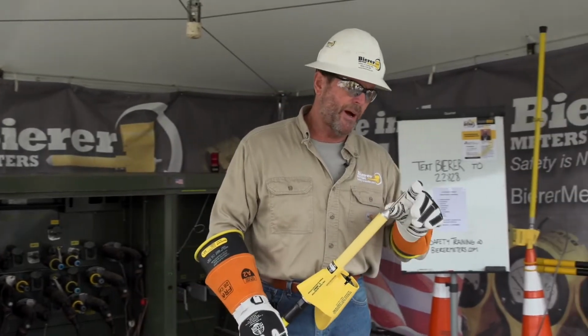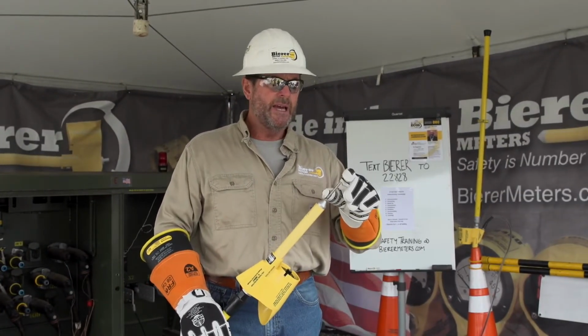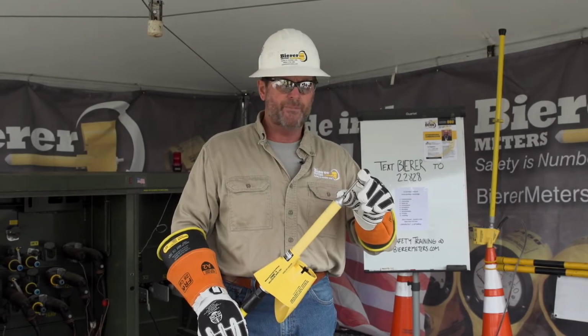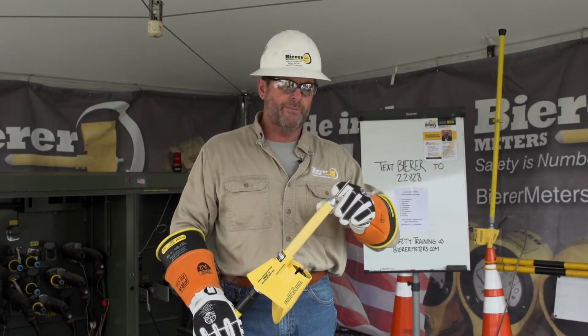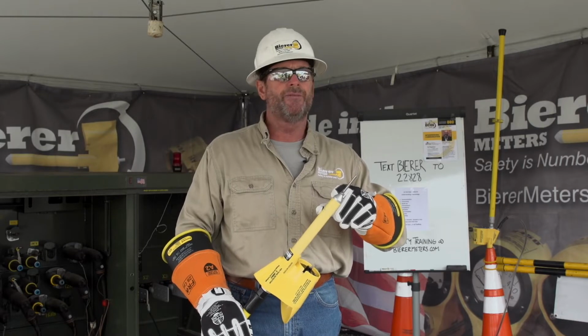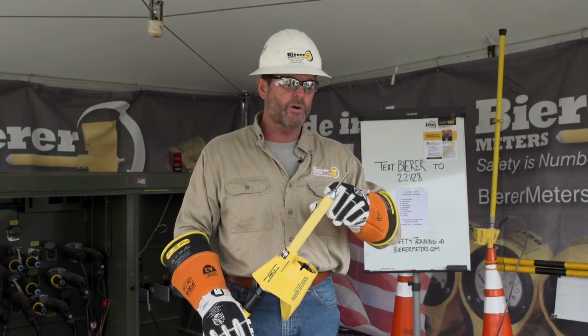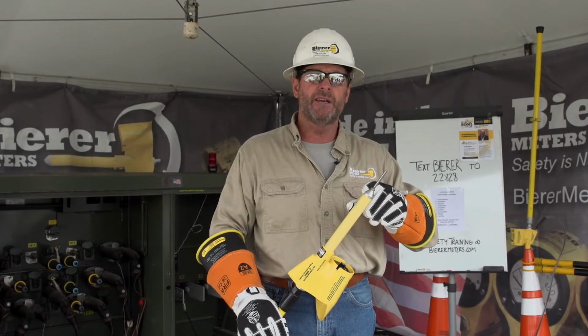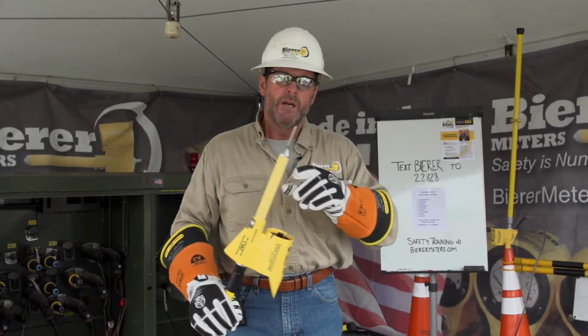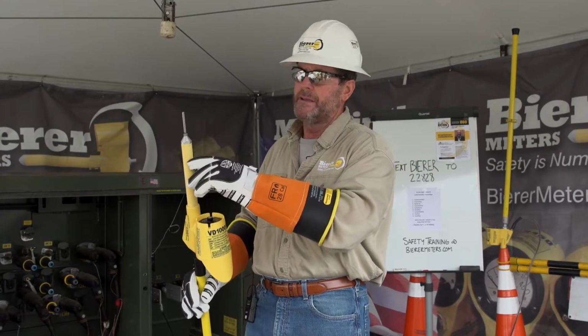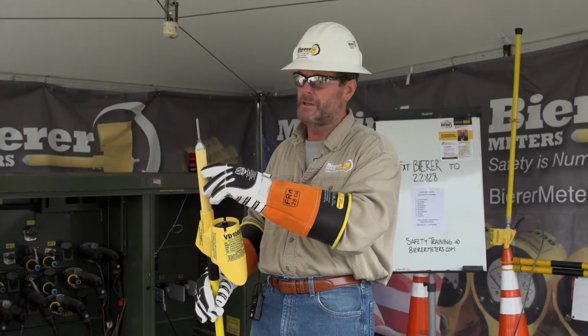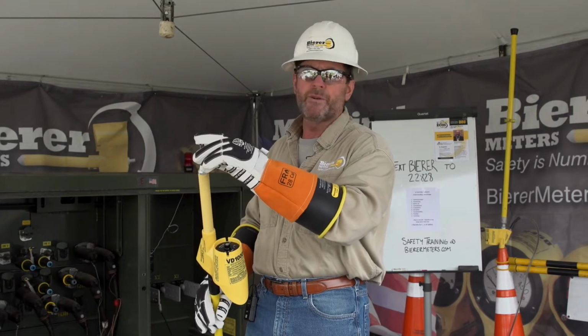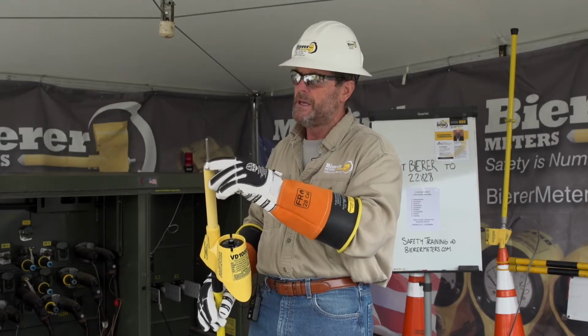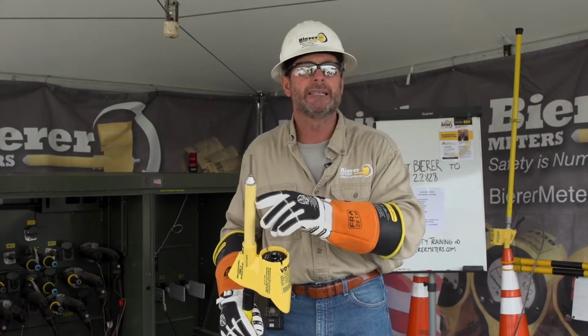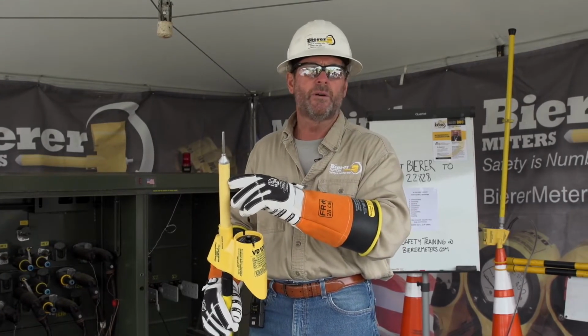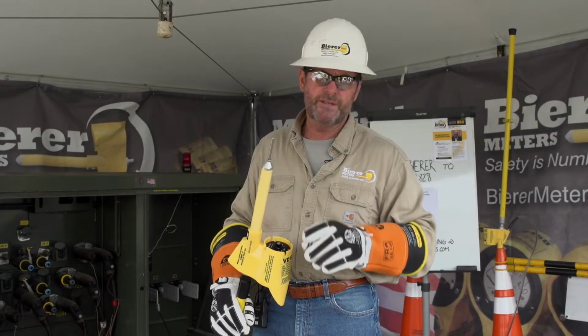If you do not have the proper accessory on, and you just simply take a shortcut, that's what it's called, a shortcut. It's not proper work method. You can simply use the end of the device, but it's a shortcut, it's not safe. Remember, it does not equal safety. You always want to make sure you do not bypass that line limit, the resistors, your protection. If you have the proper accessory on, the opportunity to bypass those resistors is much less, so it's a lot safer. See how that works? So always use the proper accessory.